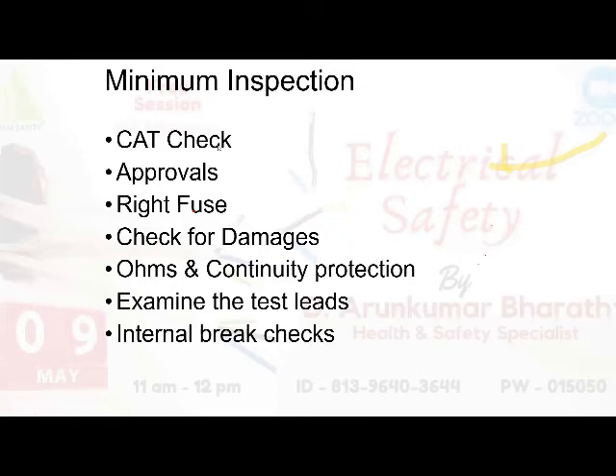First check the category, then check for approvals like CE or IEC. Check the right fuse - don't compromise on the fuse part. Then check for physical damage, making sure nothing is physically broken. Then ohms and continuity protection - this point may not be available on all equipment, but you can check. Ohms and continuity protection means even a wrong selection of the jack itself will not create electrocution.